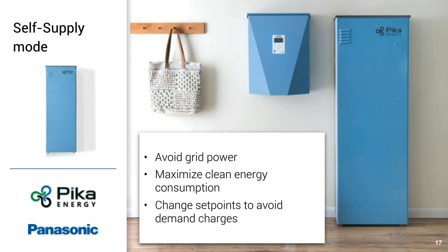Self-supply mode, again, is about avoiding grid power in markets where that's important, or if the customer just wants to maximize their consumption of clean energy. So if you have a market where net metering has been deprecated or limited, or where it's illegal to backfeed the grid, you can use zero export, which is a subset of our self-supply mode, which won't allow the inverter to export to the grid at all. It just clips at the array level. And then you can change these set points to avoid demand charges as well.